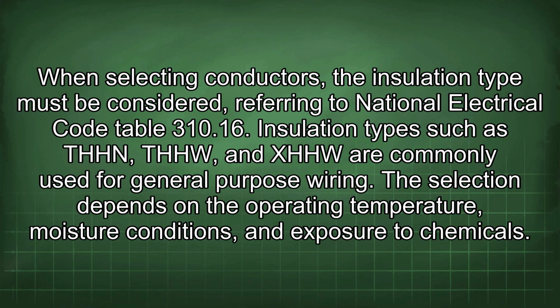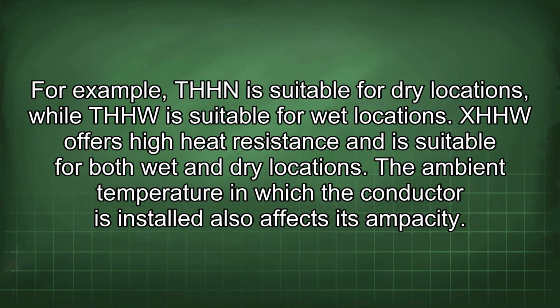When selecting conductors, the insulation type must be considered, referring to National Electrical Code Table 310.16. Insulation types such as THHN, THHW, and XHHW are commonly used for general-purpose wiring. The selection depends on the operating temperature, moisture conditions, and exposure to chemicals. For example, THHN is suitable for dry locations, while THHW is suitable for wet locations. XHHW offers high heat resistance and is suitable for both wet and dry locations.